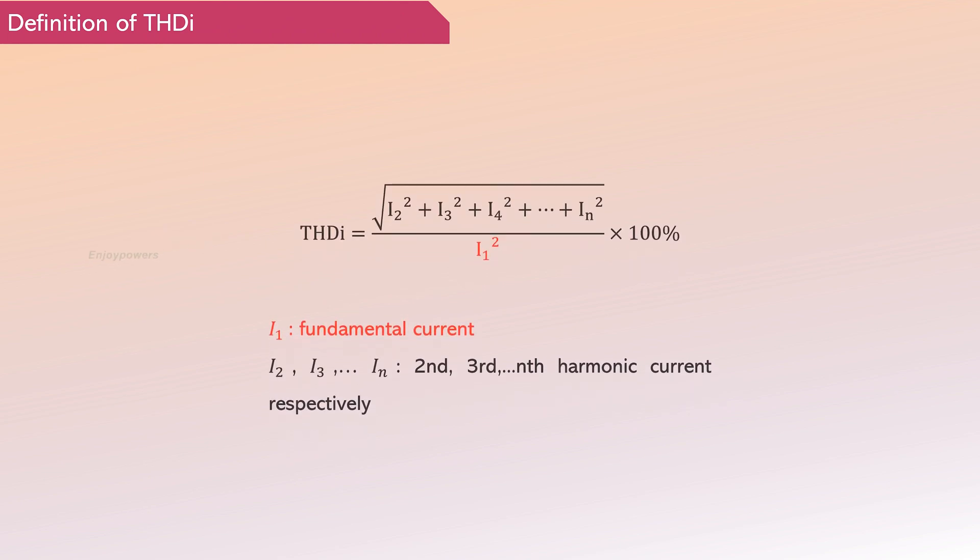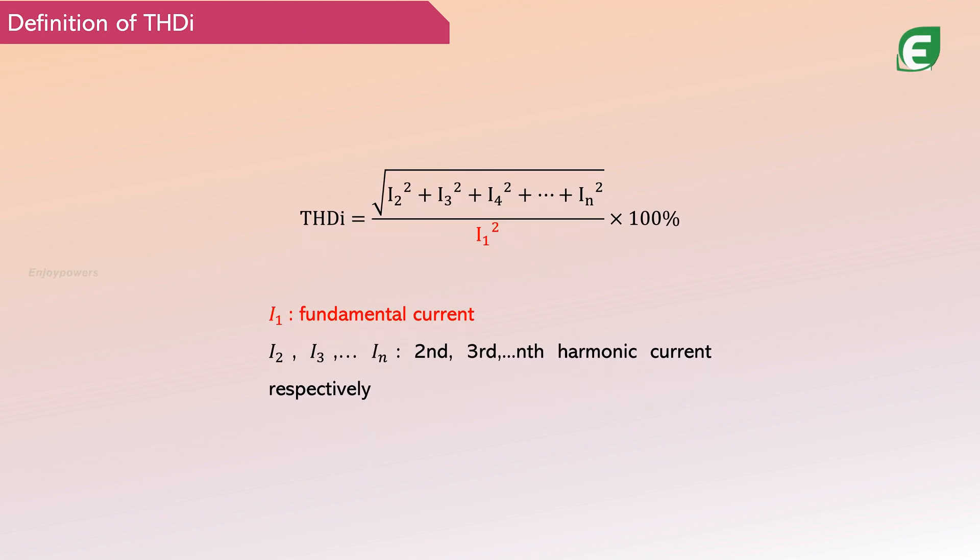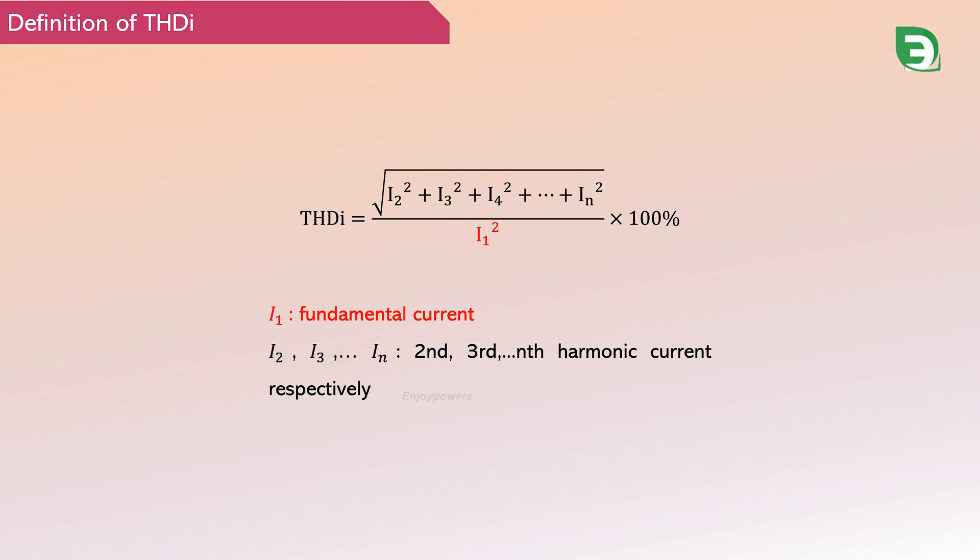The most common index for assessing the degree of harmonic impact on power quality is the total harmonic distortion. It is expressed by calculating the ratio of the sum of the effective values of all harmonic currents to the effective value of the fundamental current.